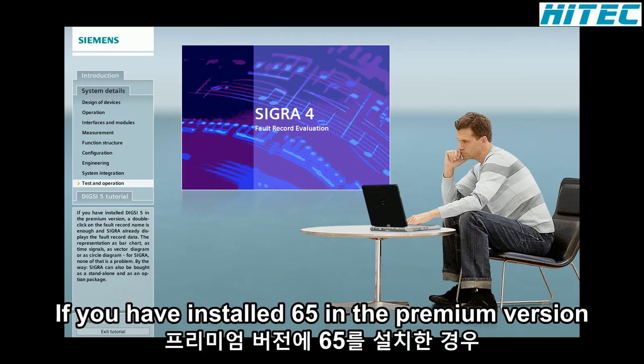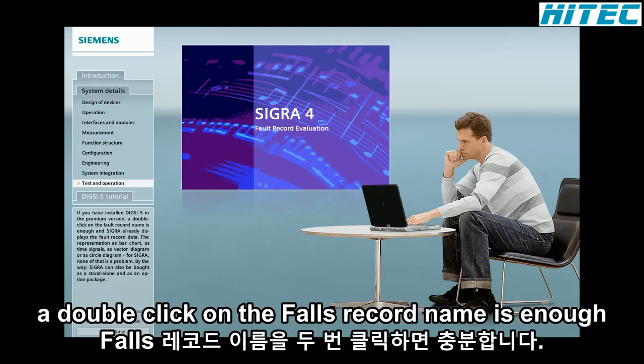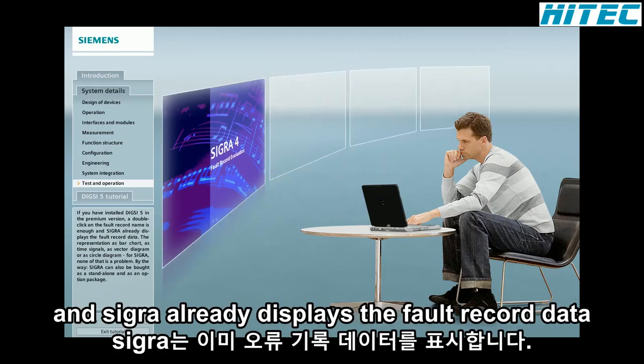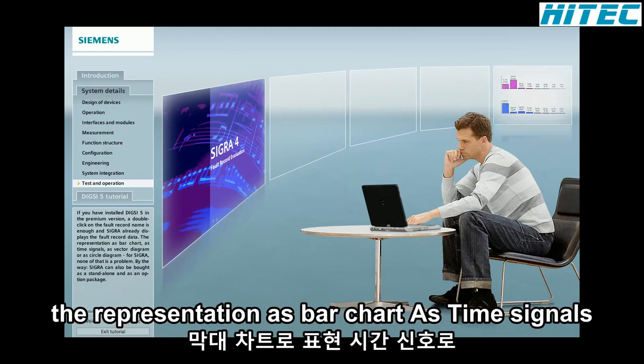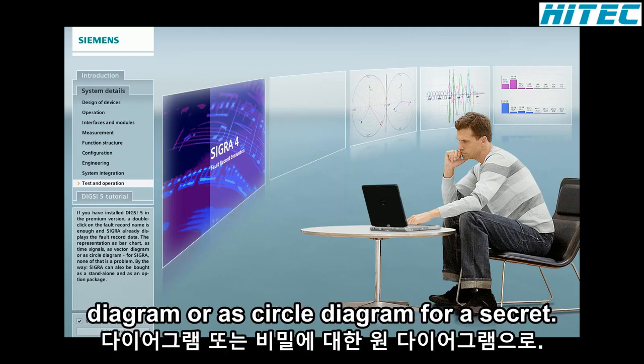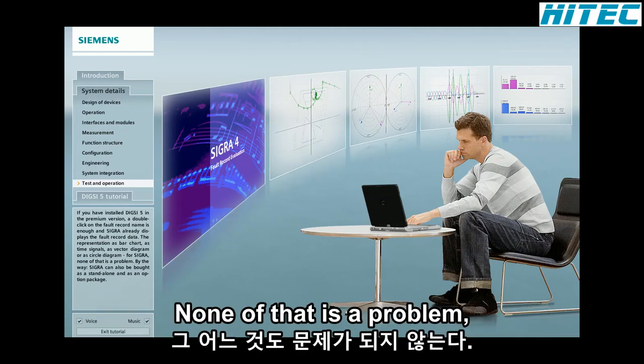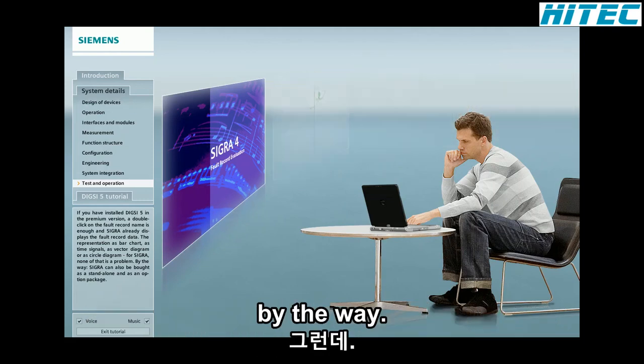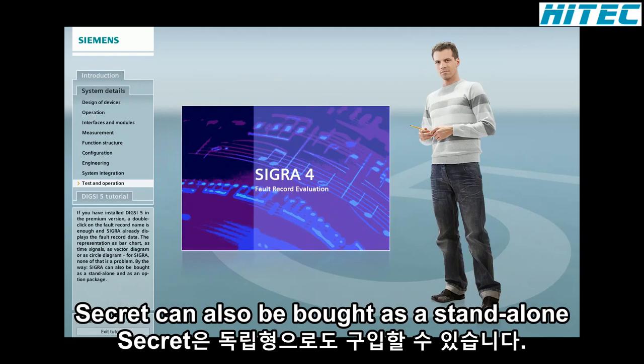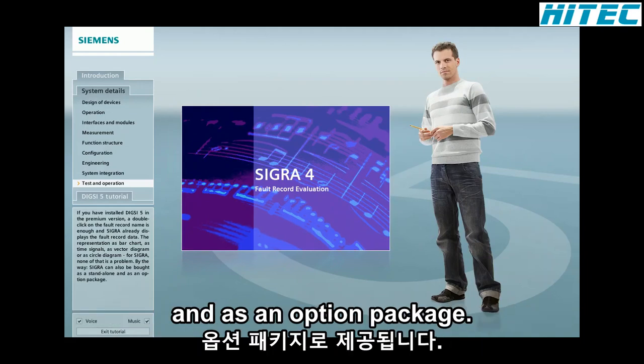If you have installed DIGSI 5 in the premium version, a double click on the fault record name is enough, and SIGRA already displays the fault record data. The representation as bar chart, as time signals, as vector diagram, or as circle diagram, for SIGRA none of that is a problem. By the way, SIGRA can also be bought as standalone and as an option package.